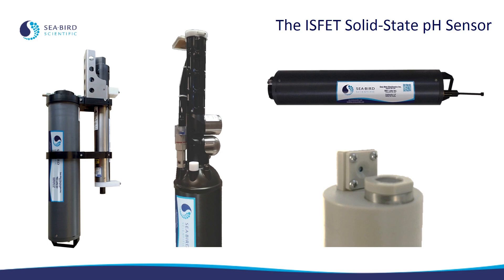Seabird's solid state pH technology is being used both in profiling floats and in moored SeaFET and SeapHOx sensors. We are really excited about this technology because it provides superior pH accuracy and resolution compared with traditional glass bulb based pH sensors. And because it does not rely on a liquid filled electrode, the solid state pH sensor is much more stable in seawater and does not require as frequent of servicing. Thank you so much for watching. If you have any questions, please reach out to the sales team at Seabird Scientific.